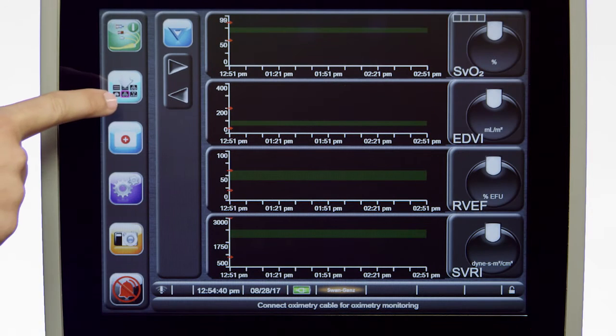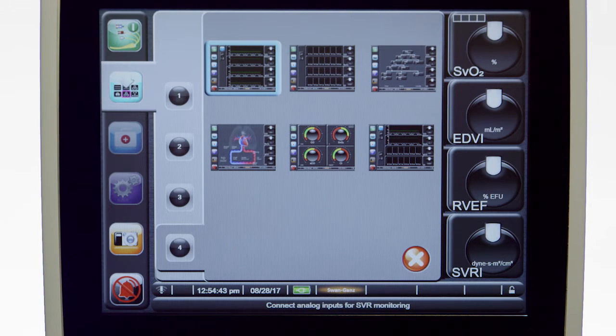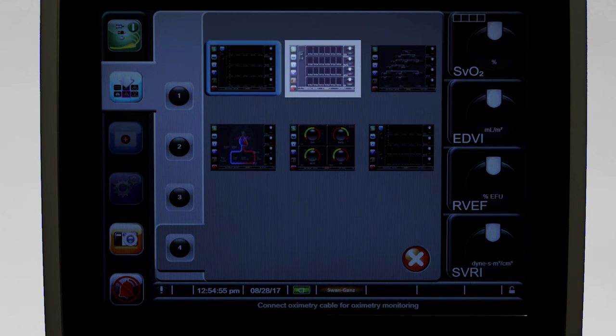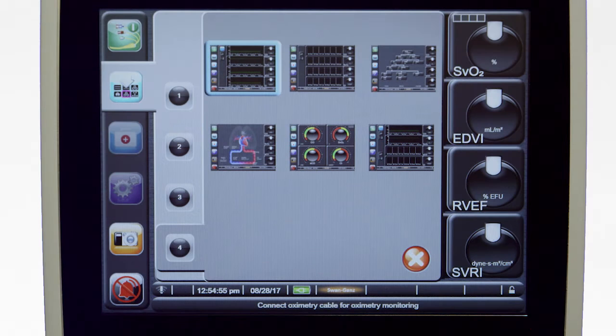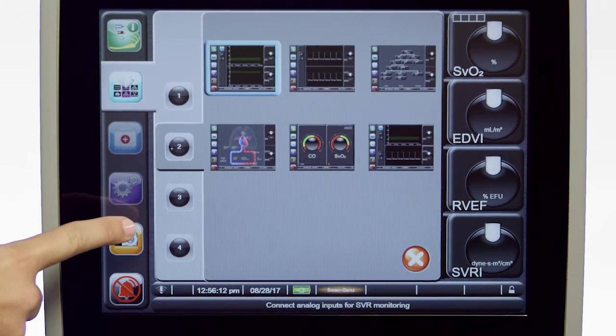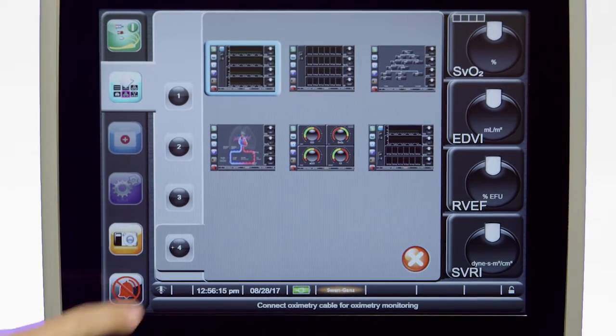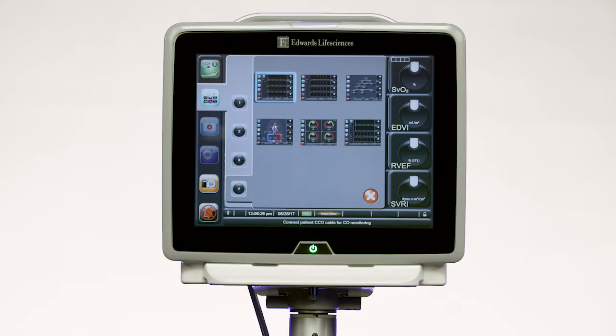Touch the Monitor Screen Selection icon to choose between the various data display screens available for the main window area. To return to the most recent monitoring screen displayed, touch the Cancel icon. The display screen options are Graphical Trend, Tabular Trend, Physio Relationship, Physiology, Cockpit, and Split Screen. Up to 4 monitored parameters can be displayed on these screens at one time. Touch the circled number 1, 2, 3, or 4 that represents the number of key parameters to be displayed on the monitoring screen. Choose the desired display screen.